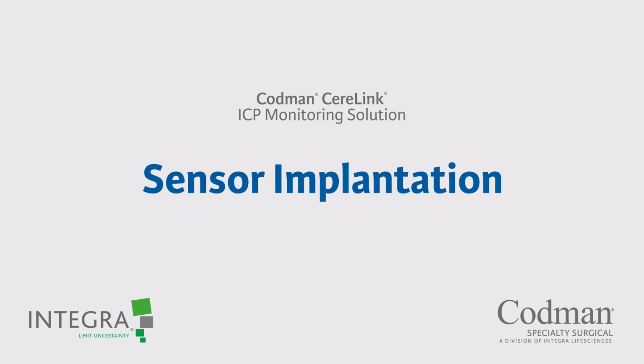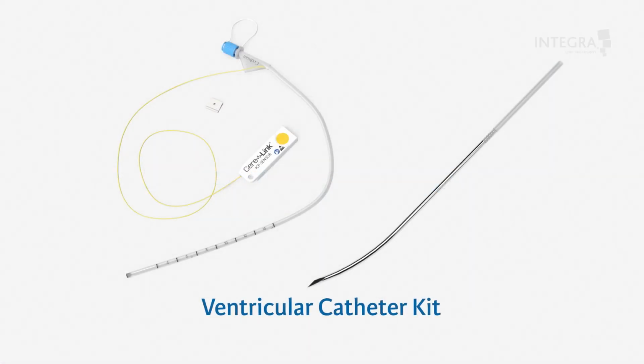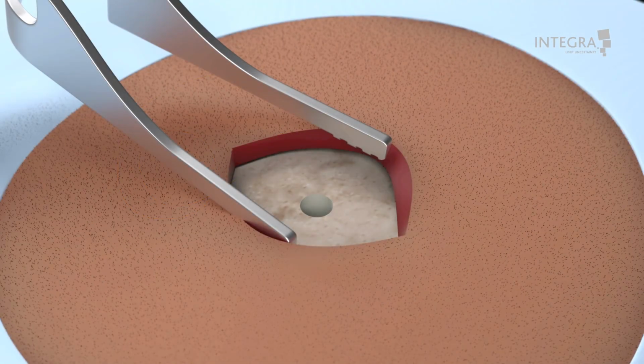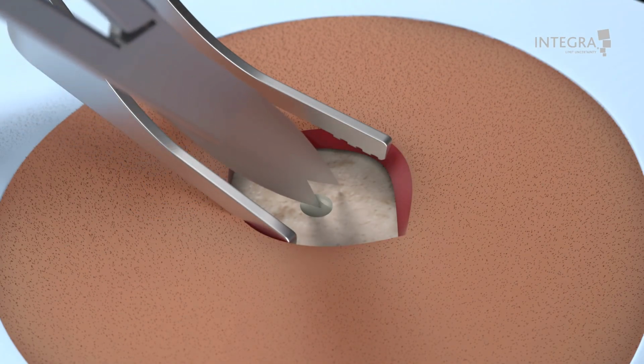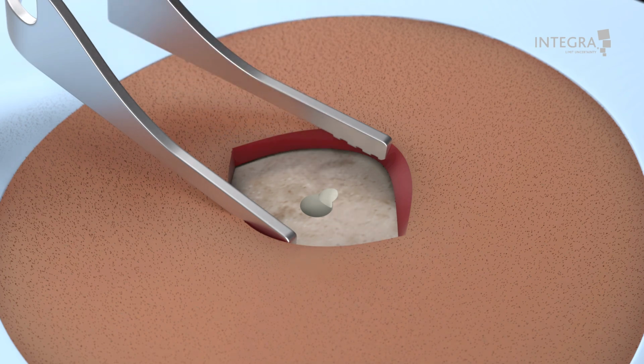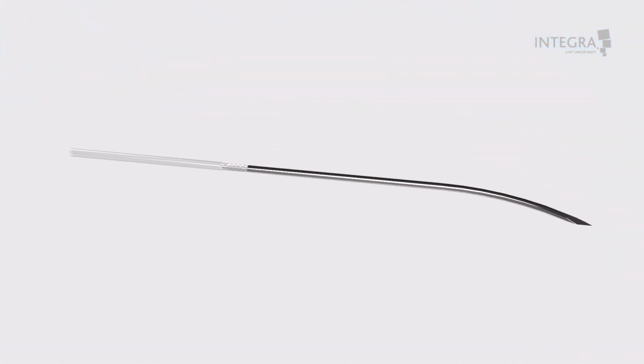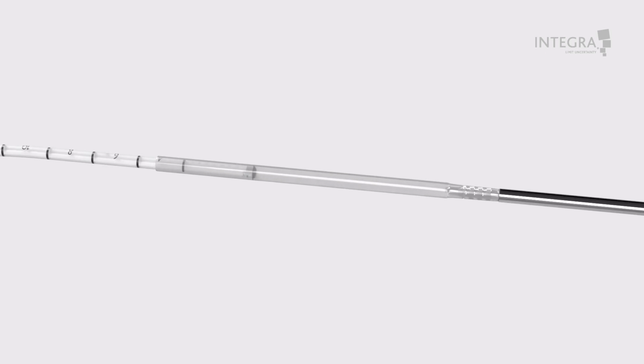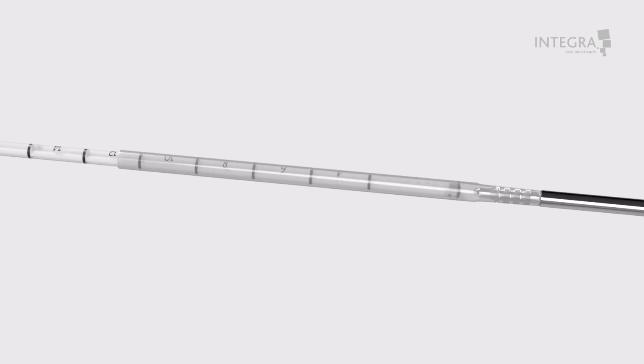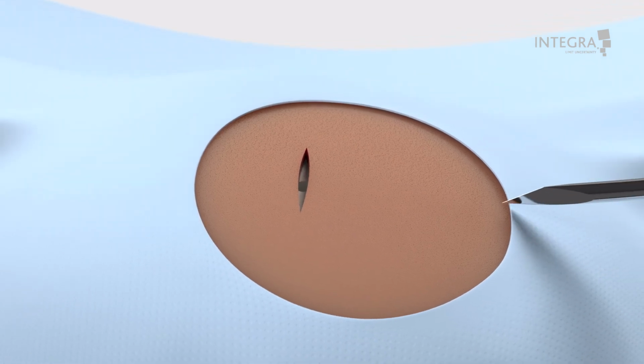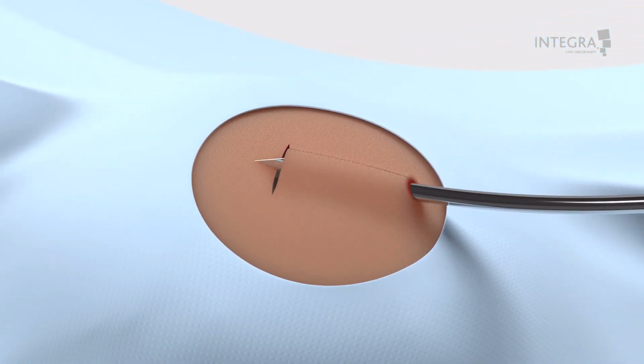3. Sensor implantation. The ICP sensor ventricular catheter kit includes a 38 cm ventricular catheter with an integrated stylet and intracranial pressure ICP sensor, a catheter anchoring clip, and a 7-gauge tunneling trocar. Gently bevel the burr hole on one side to allow the catheter to exit without a sharp angulation. Insert the tip of the catheter into the end of the clear tubing of the tunneling trocar until the tubing is filled. Use the tunneling trocar to tunnel the ventricular catheter under the scalp to the craniotomy site.